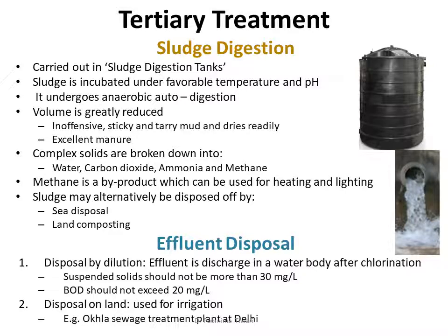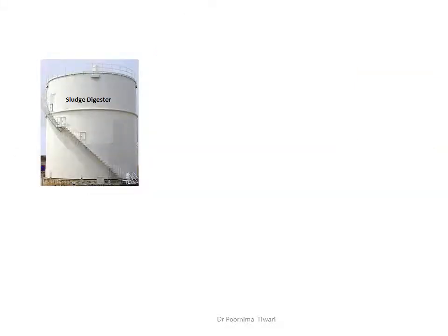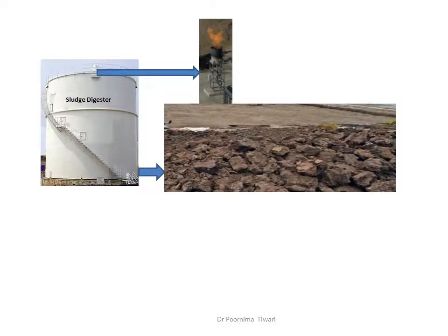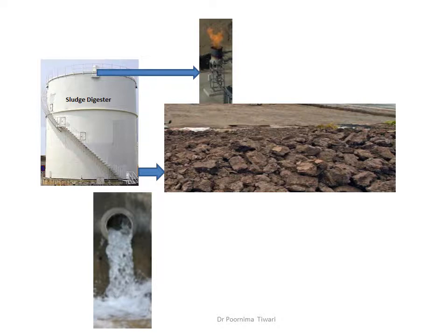A pictorial representation shows the sludge digester as an enclosed tank with no air entry, enabling anaerobic oxidation. Methane rises above and can be used as fuel, and the reduced-volume sludge can be dried in sludge drying beds and used as fertilizer. The effluent from secondary sedimentation can be disposed of by dilution into a water body after chlorination — provided suspended solids do not exceed 30 mg per litre and BOD does not exceed 20 mg per litre — or used for irrigation, as is done at the Okhla treatment plant in New Delhi.